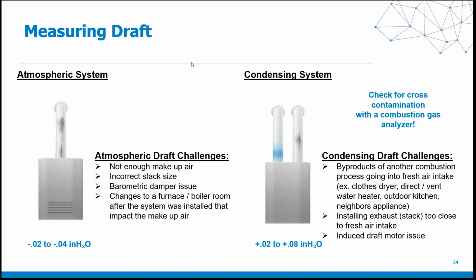The way that you do it is you simply put your probe into the fresh air intake for a condensing system, as close to the breech as possible. So, for example, you put your probe into this fresh air intake and you take a reading of what the oxygen is. That oxygen should be 20.9%, because you're measuring the fresh air incoming into that system from the outdoors, and it's 20.9% oxygen in the air that we breathe outdoors. If you don't have 20.9 and it's 18.2, 16.4, or whatever, you have cross-contamination.